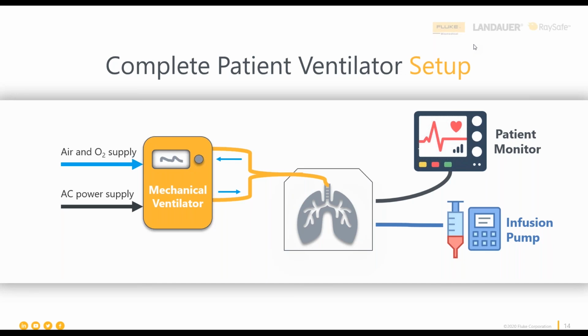And all of these devices are critical to the diagnosis and the treatment of a COVID patient. And all of these devices need to function properly. So one thing to note is that all of the medical devices displayed here are powered by electricity. So in order to ensure that these medical devices are safe to use for both staff and patients, electrical safety testing needs to be performed. Once that's done, the second portion of testing is functional testing. Functional testing ensures that the patient monitor is displaying the right readings, the infusion pump is infusing the right volumes, and the ventilator is delivering the right flow, pressure, and volume.